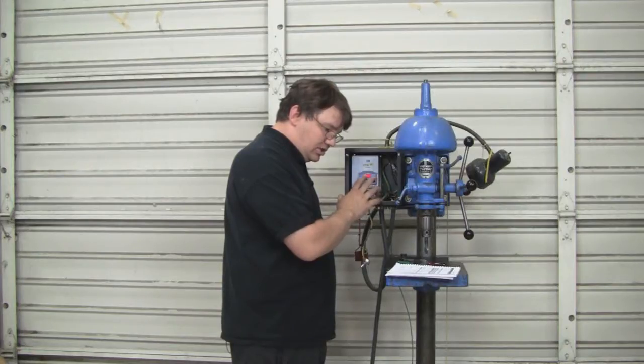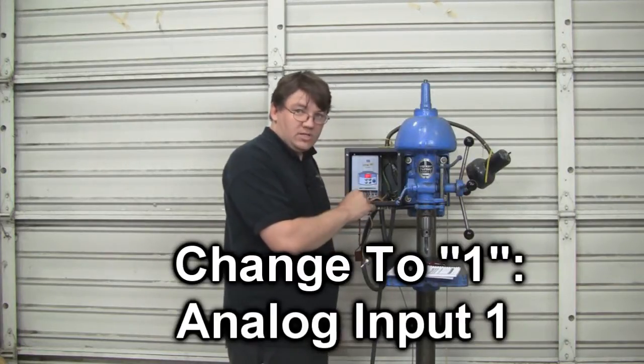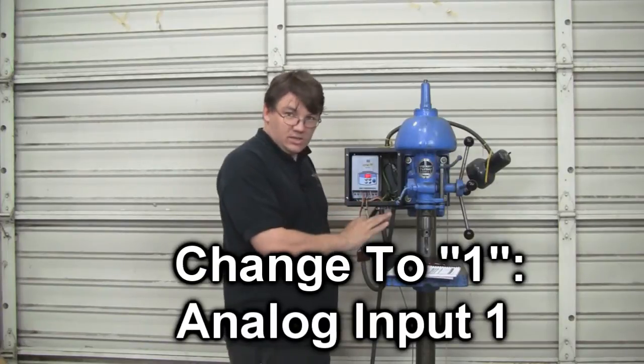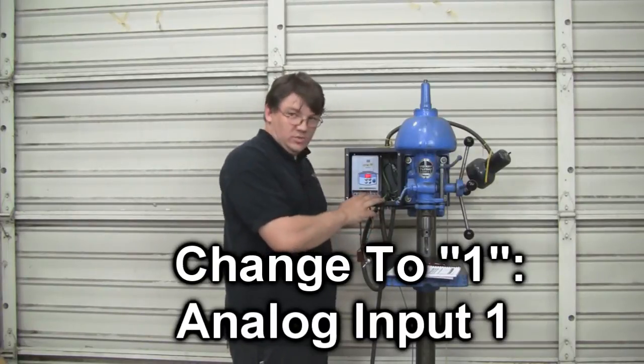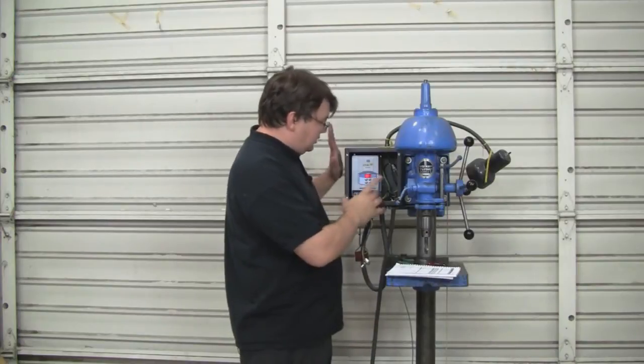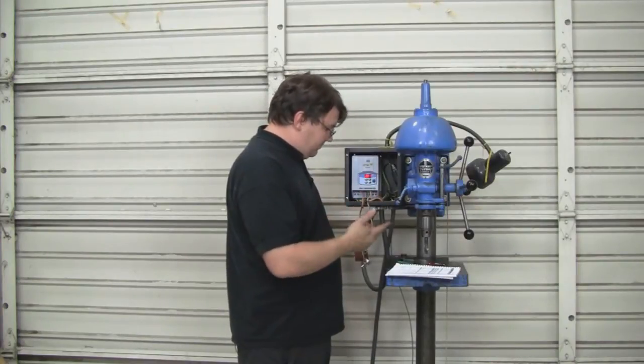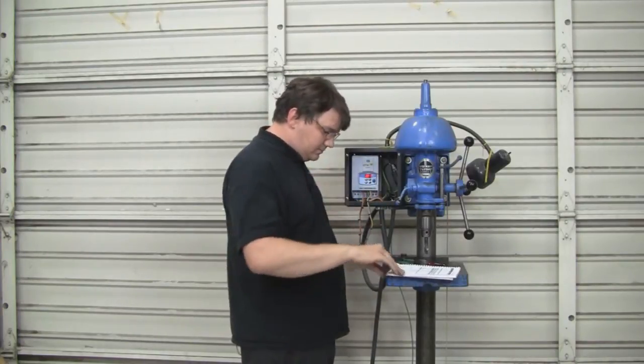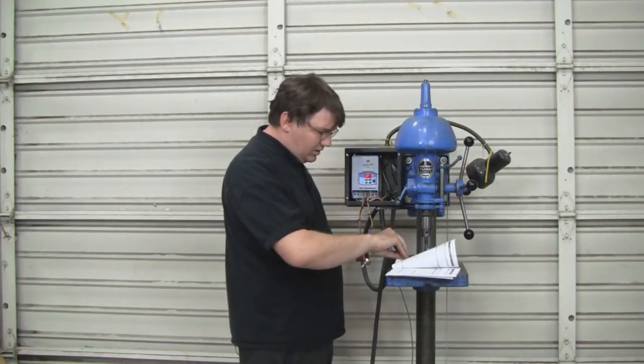But we want to go ahead and change this to 1, which corresponds to analog input 1. That tells it to listen to the potentiometer for a voltage, which will translate into a speed. We go ahead and add 1, and then we're going to save that.